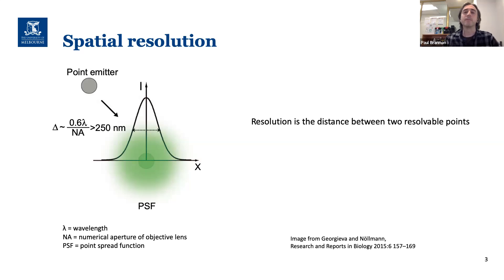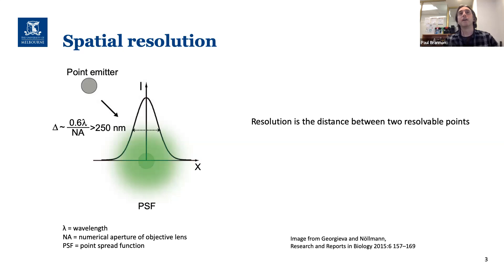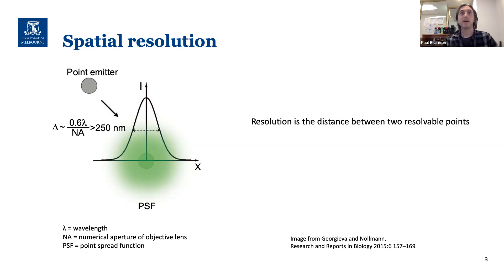One of the problems if you've done fluorescence imaging is you can't quite resolve everything — you want more resolution and you run into something called the diffraction limit. That limit comes at about 250 nanometers. So if you're interested in looking at bacteria, nanoparticles, exosomes, extracellular vesicles — you're not really going to be able to resolve these, meaning distinguish two very close objects from each other. This resolution limit is derived from the wavelength and the numerical aperture of the system — your objective lens and the glass the light travels through before reaching your detector.